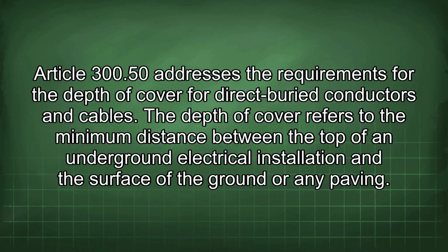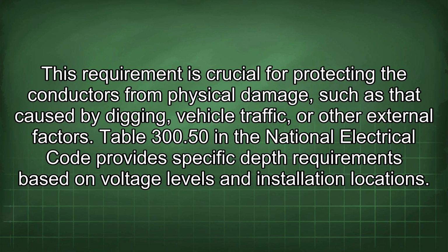Article 300.50 addresses the requirements for the depth of cover for direct buried conductors and cables. The depth of cover refers to the minimum distance between the top of an underground electrical installation and the surface of the ground or any paving.